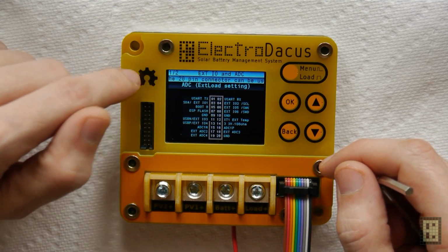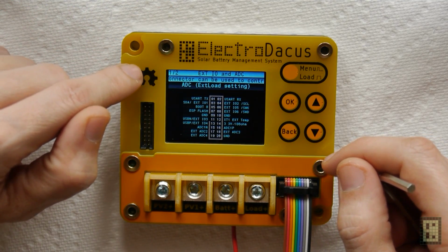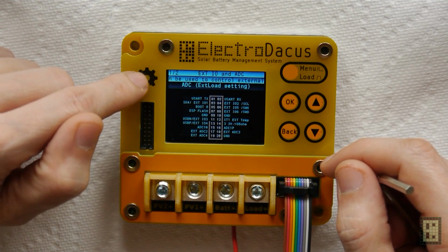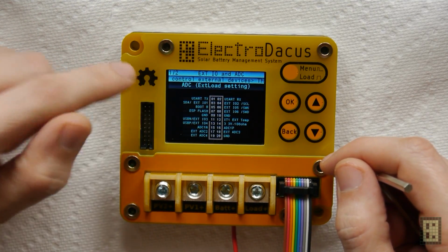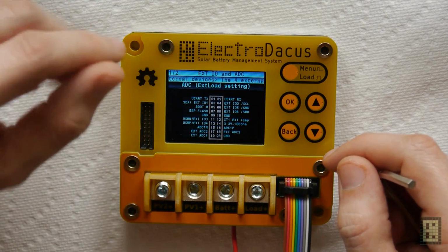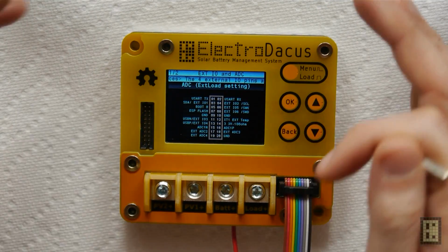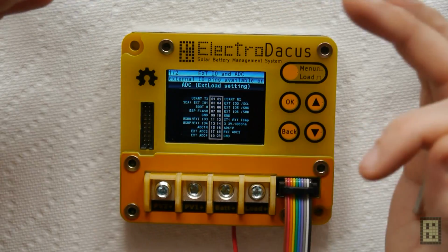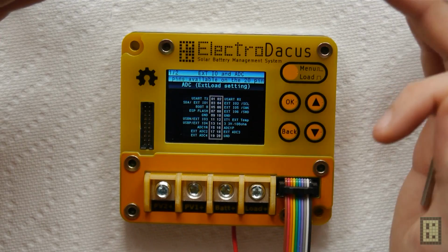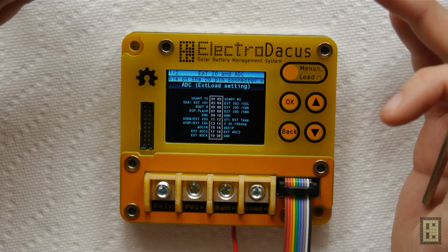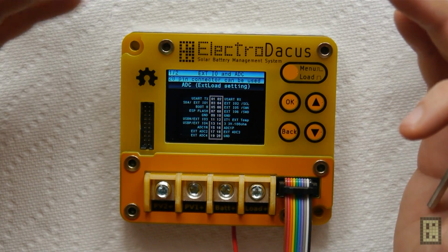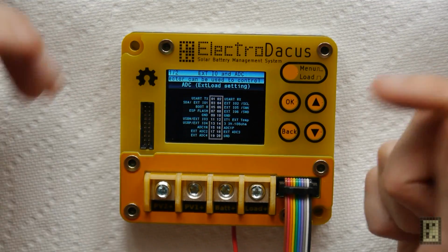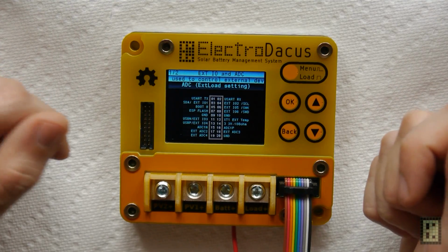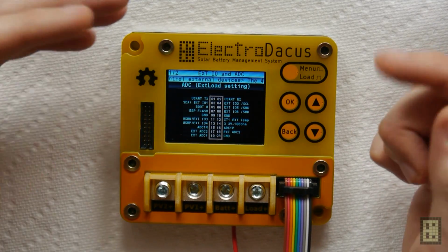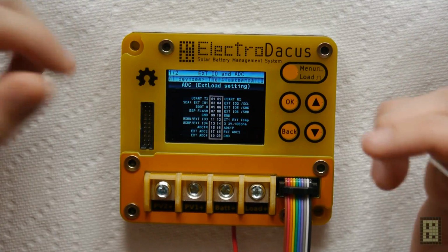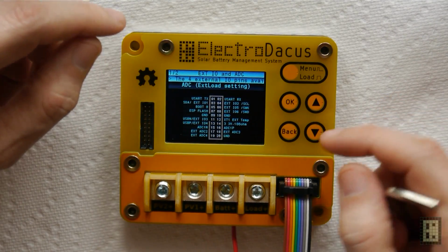If you look in the solar BMS basic manual, I explain in quite a few details the way you connect an external load. The external load on a 24 volt system can be up to 12 kilowatts of power, 12,000 watts. That's probably more than you need. I don't think there are inverters or any DC loads that require more than 500 amps.